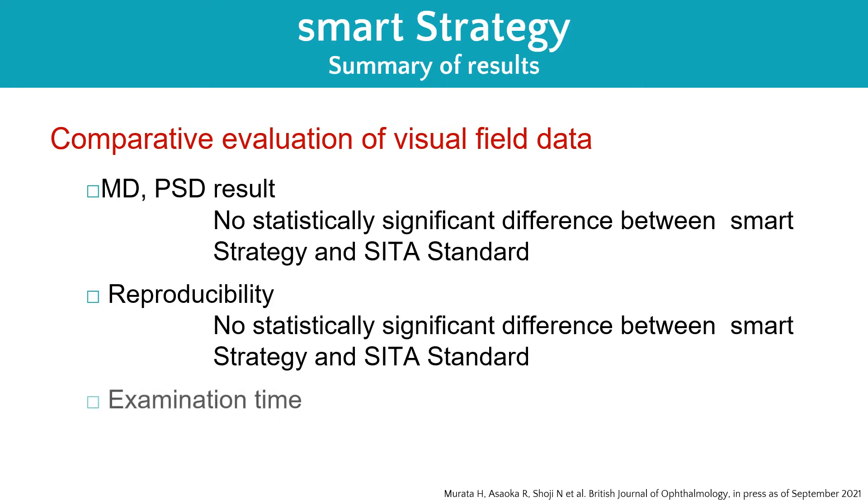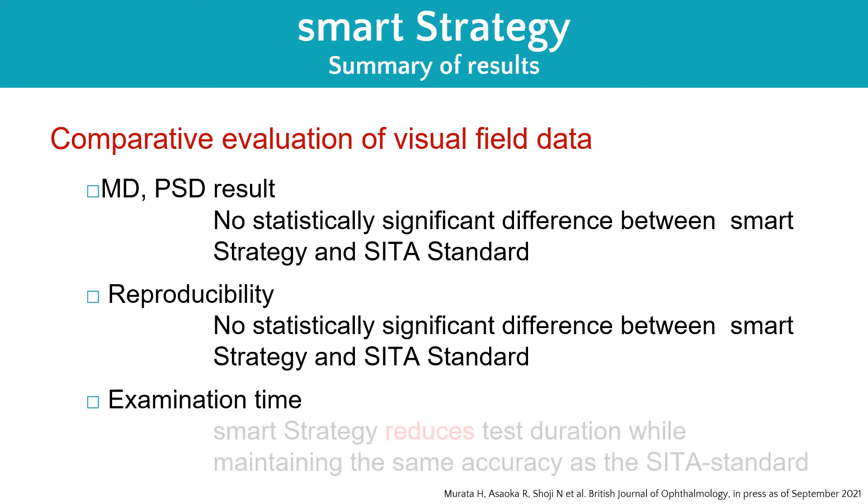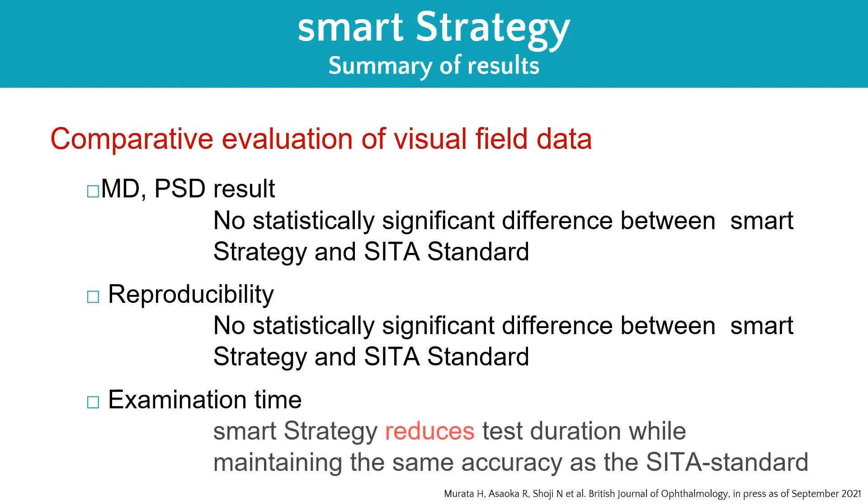This is the summary of actual measurement results. No statistically significant difference is observed in mean deviation, pattern standard deviation results, and reproducibility between SMART strategy and SITA Standard. SMART strategy also reduces test duration while maintaining the same accuracy as the SITA standard.